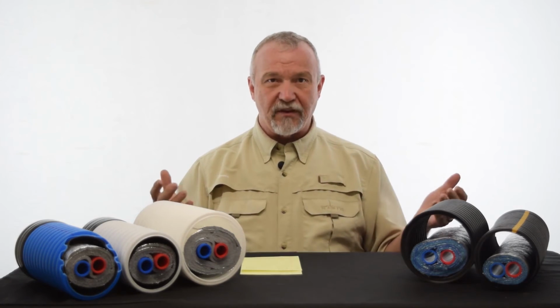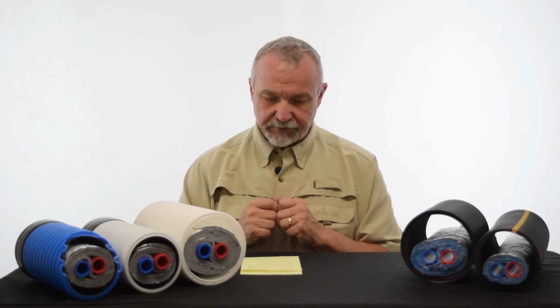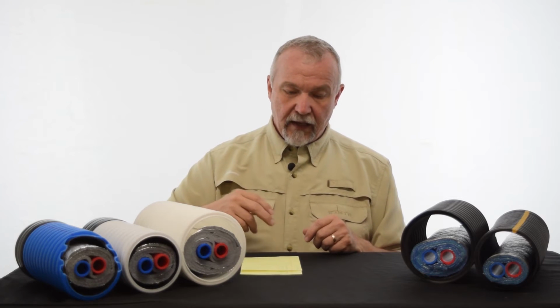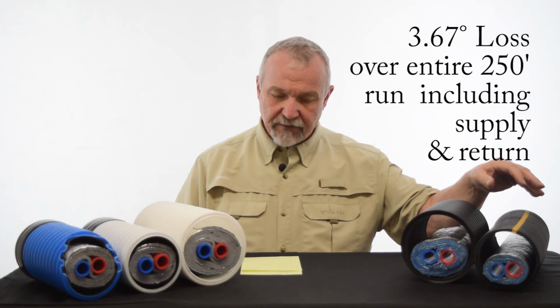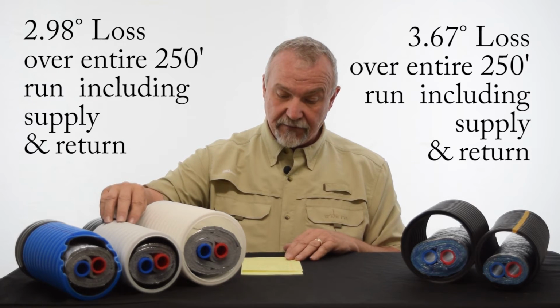Quite frankly, we don't think this kind of top-of-the-ground testing is realistic and would never use it in our day-to-day marketing. But for this test, since it is how they do it, it is useful. Here are the results. In the 250-foot run, all the way down and back, the competitor's pipe lost 3.67 degrees, while the Z Supply insulated pipe lost 2.98 degrees.